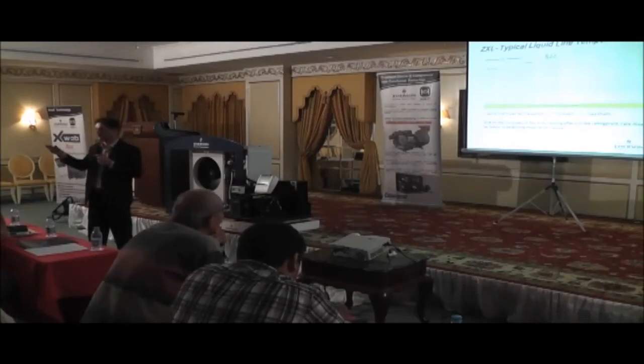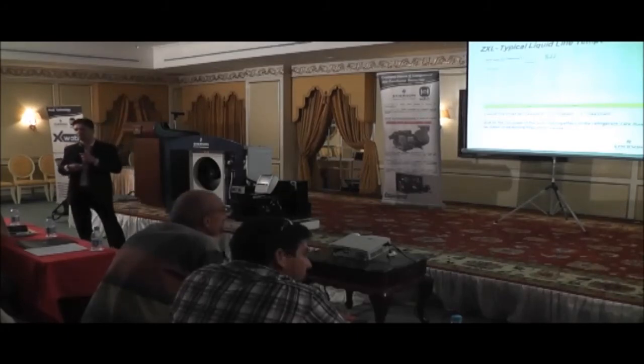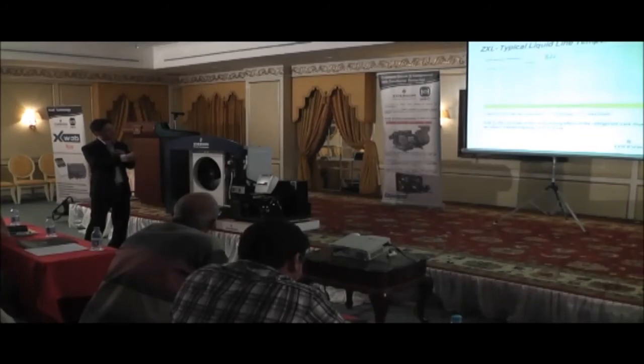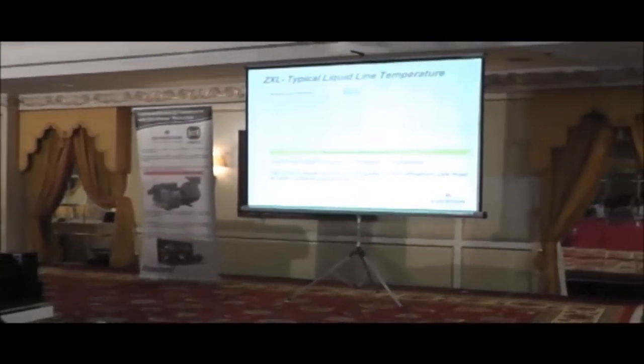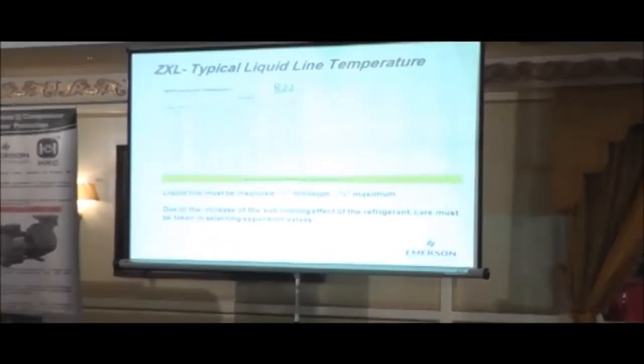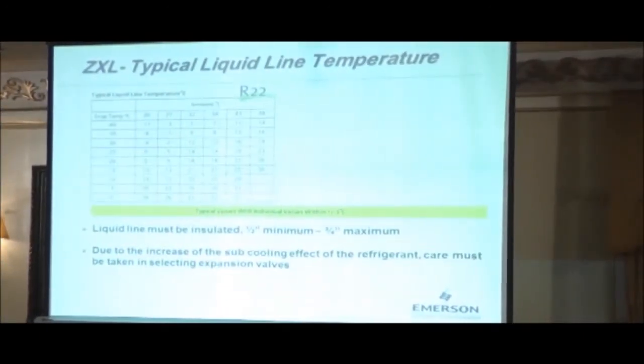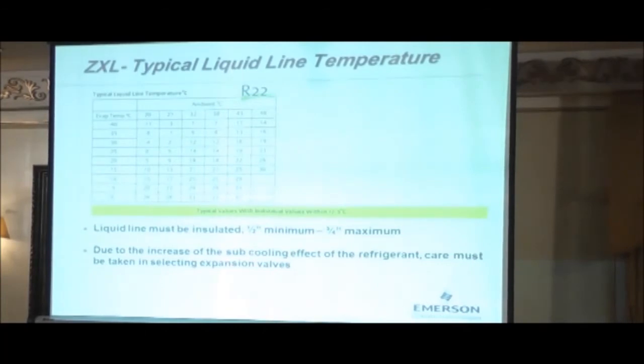All right. So traditionally, if you were condensing at 50, your liquid line would be at 47. You would have 3K subcooling. But then in this application, your liquid line is going to be a lot cooler. So just as an example, if you're running a freezer room at minus 25 and your ambient is 48 degrees C, your liquid line will be 23 degrees C. It's much, much, much cooler. By introducing cooler liquid into the indoor coil, we increase the capacity of the coil. So this is how we get the extra capacity.